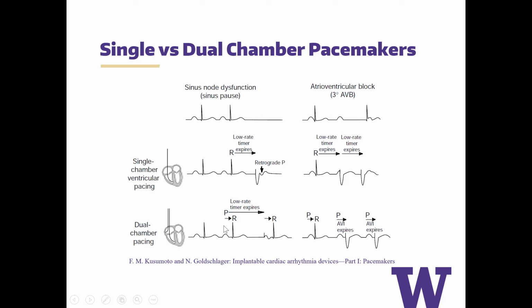so it has an atrial lead, when you have a last sensed P wave, it will start a timer. And then when you have a last sensed R wave, it will start another timer. And so in pacemakers, it's all about timing. Both of these timers will go on at the same time. This first little timer is actually the AV delay or the AV interval, and this interval is most similar to what we think of as the PR interval. And then it will also start the low rate timer.